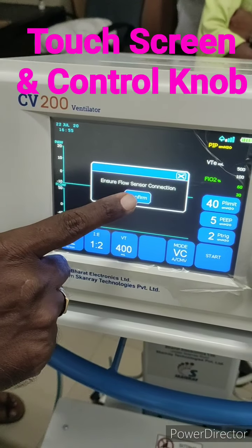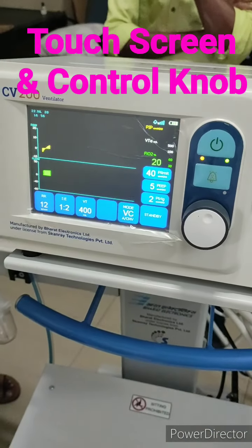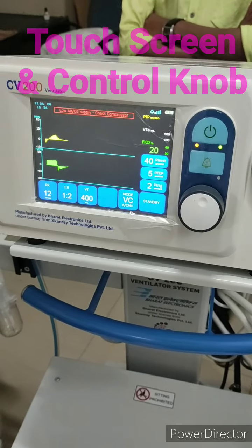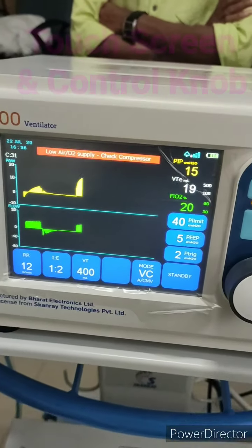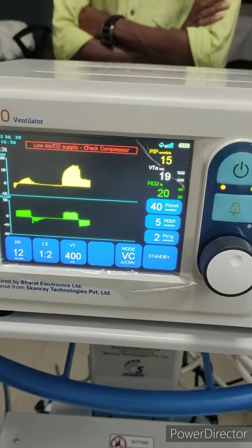Sensor connection. Ensure flow sensor connection. Confirm. Yes. So machine has started. Now it is giving the alarm of low air or oxygen supply. Check compressor.